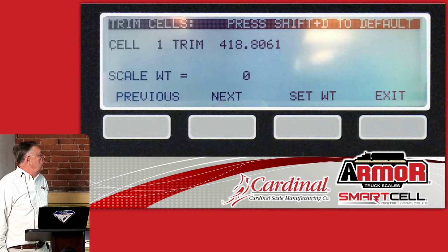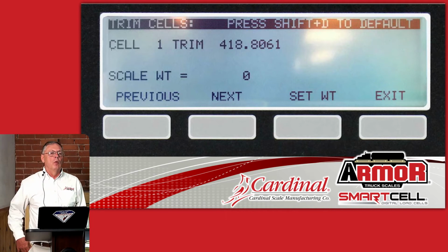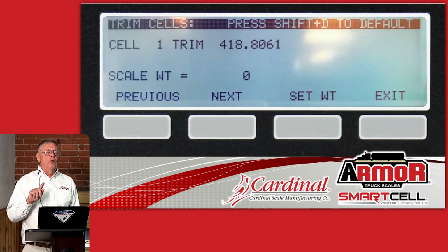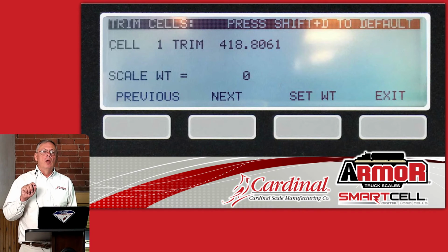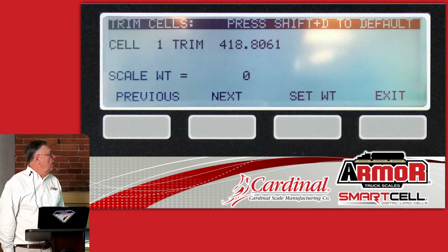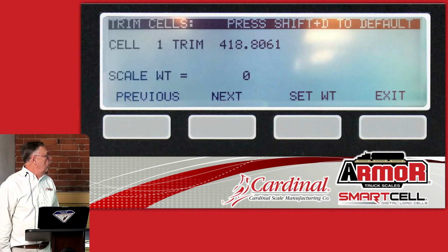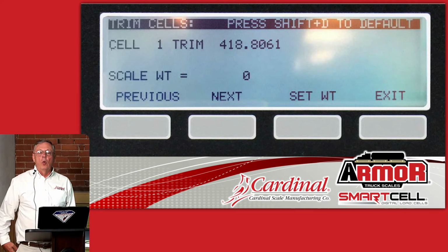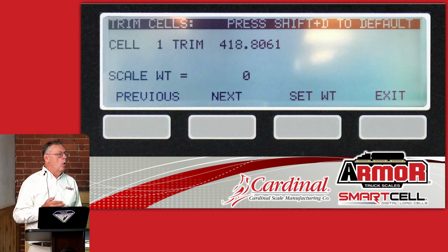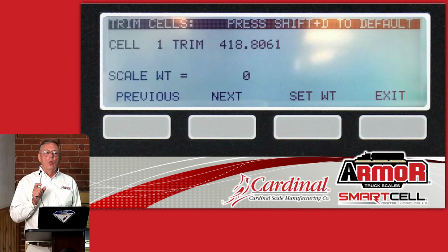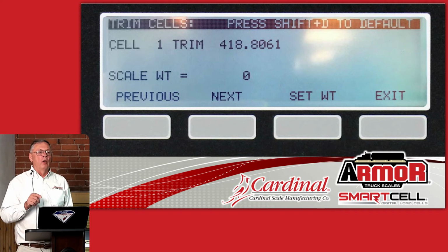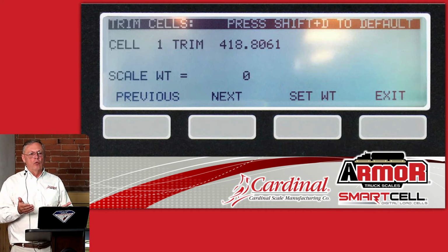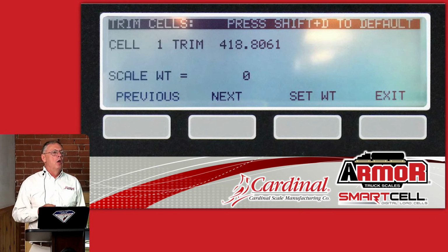The system here is a little bit different and a lot simpler to use than previous systems. Previously on the ICANN or on our SnapStream system, if you needed to raise the output of a load cell 40 pounds, you had to push the up key, sometimes multiple times, to make that happen. And there's really no reason to do that. On the new SmartCell technology, if your test cart weighs 21,000 pounds and you want to adjust cell 1, you just park the test cart on cell 1, push the third button over that says set weight, you tell it you want that load cell to be reading 21,000 pounds, press enter, we do the math and automatically change that. So there's no more pressing up and down keys multiple times to try to get that weight adjusted. It makes it very, very easy to adjust the load cell.